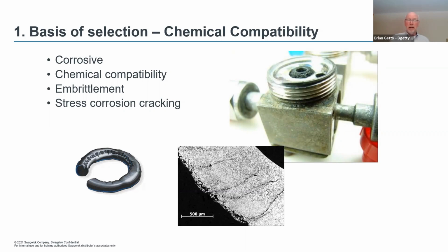And again, this is metal. This is a product that was passing through the valve that created all this damage. So just to let you know that there are systems out there which are quite dangerous, and fluids that are quite dangerous, even for people and for different types of metals. This photo right here is the actual seat of the valve. You can see how it's been completely eaten up and attacked by the hydrogen sulfide. So again, it's a bit of a difficult application.